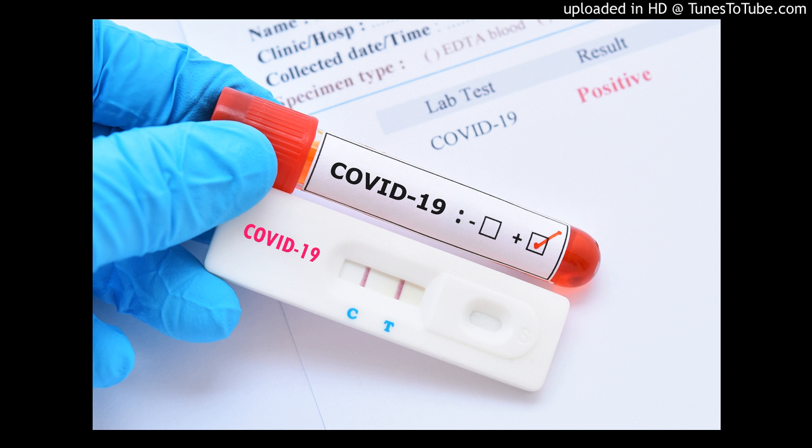So a lab will want to look at the data and be able to get a kit and test it against the existing kit that they are using. Like I mentioned earlier, looking at the validation process, you want to see if what the manufacturer says is working. So you will test it against known positive and known negative samples and look at what we call the sensitivity and the specificity. So you will be able to make a decision to say, yes, this test is sensitive enough for me or for my country or for my lab. We make a decision based on this technical data to use this kit because we feel that this is a good kit for us.